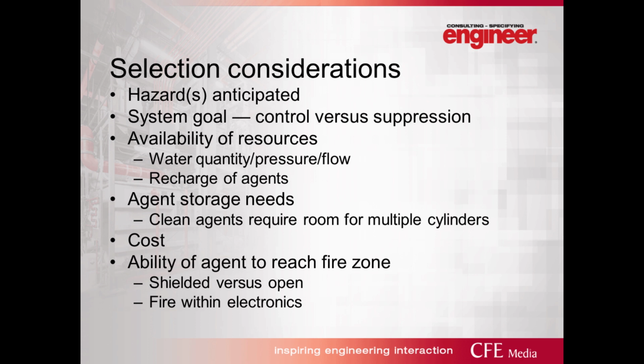Obviously, you should be looking at what the hazard is. A lot of times water is great, but in certain cases, water doesn't play well with certain hazards, and you should be looking at non-water-based suppression systems for those applications. The system goal: what are you trying to do? Are we trying to just control a fire, or is there actually a suppression or extinguishment mechanism that's important for that specific goal?